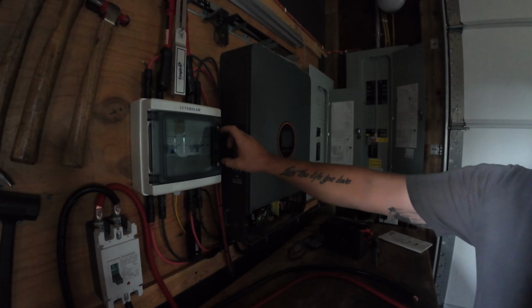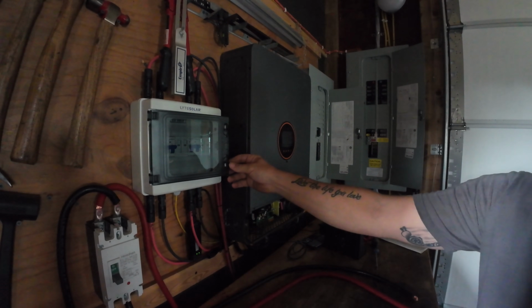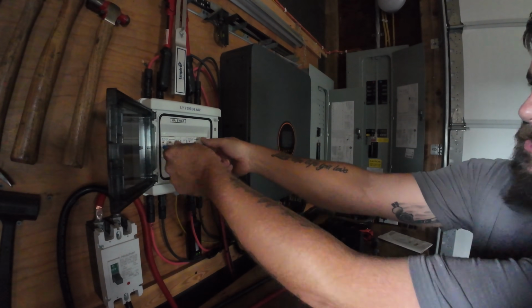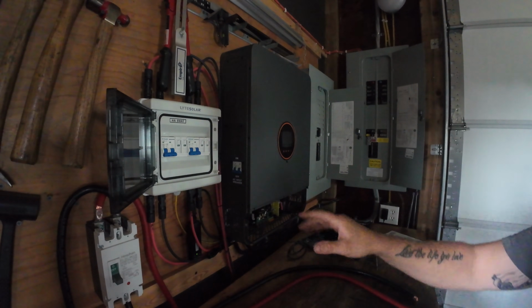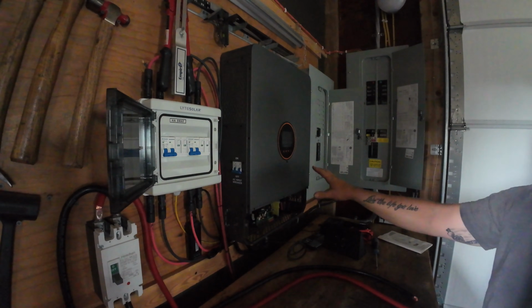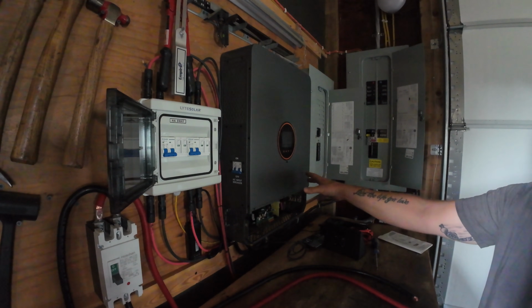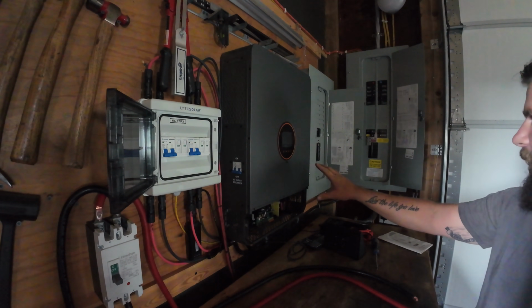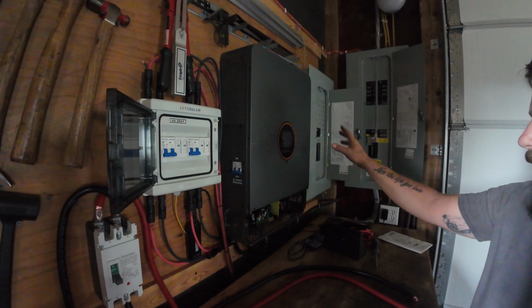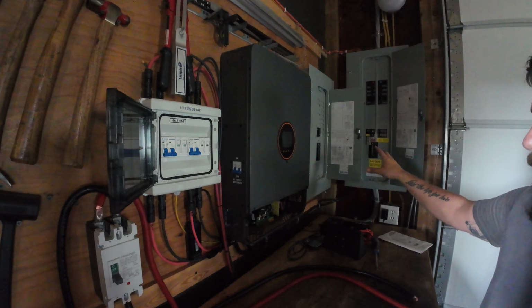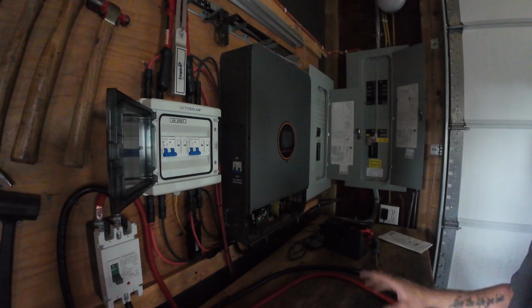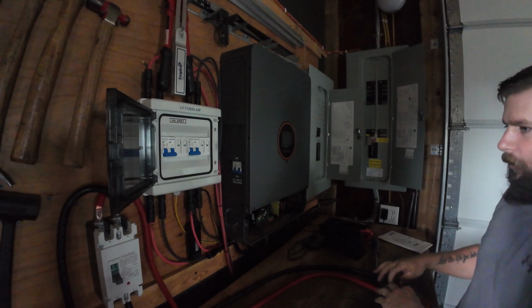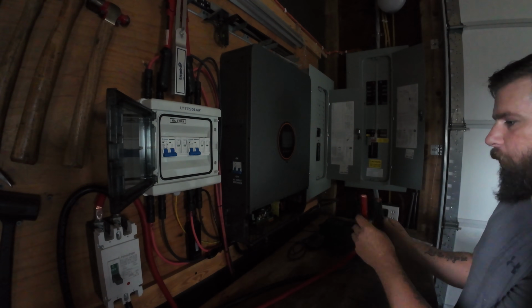And then the last step here is turning off the PV breakers. We can turn these off at the same time. So now we have no loads at all going into this inverter, no DC power. As you can hear, it just shut off completely, all the fans and everything. We've got no DC power, no AC power, no power being put out. We're completely off now, and we're safe to work on the unit itself, or to make a modification, or to add something like we're doing here.